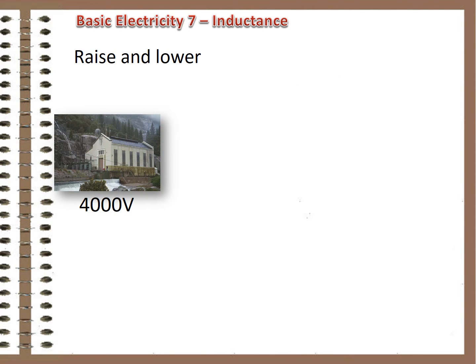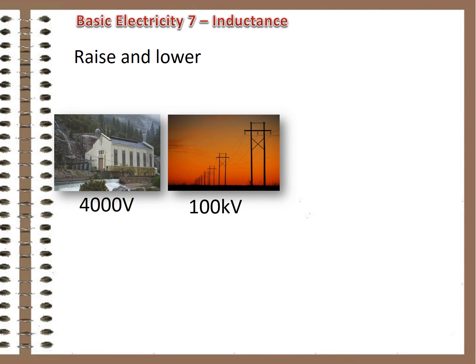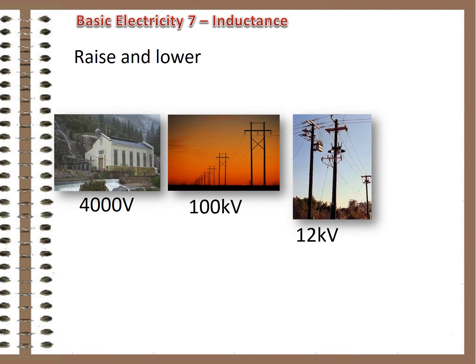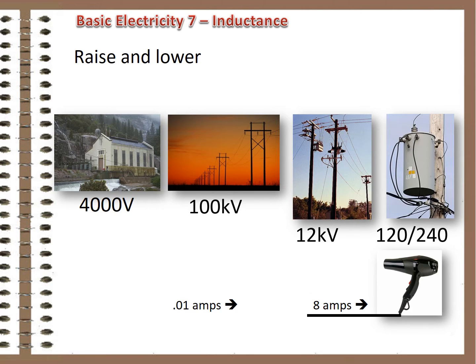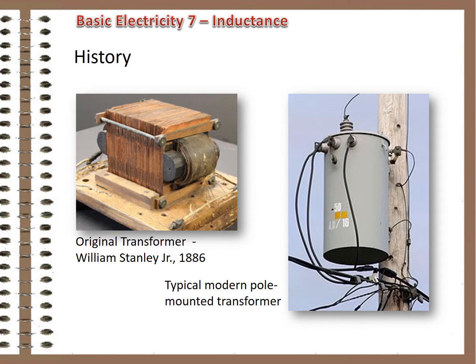So we might generate power at, say, 4,000 volts, raise the voltage up to 100,000 volts in order to move it a long distance, drop it down to 12,000 volts to distribute it locally, and then drop it to 240 or 120 volts to bring it into your house. So the 8 amps of current that it takes to power your hairdryer at 120 volts was transmitted to you at 100,000 volts and one one-hundredth of an amp of current. Transformers allow us to make those changes easily, and their invention in the 1880s led to the development of modern AC systems.